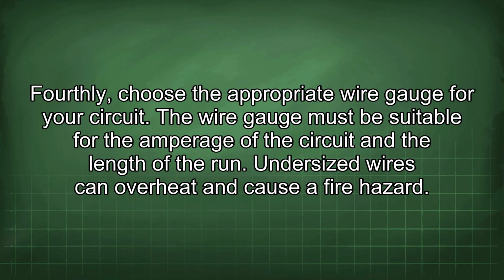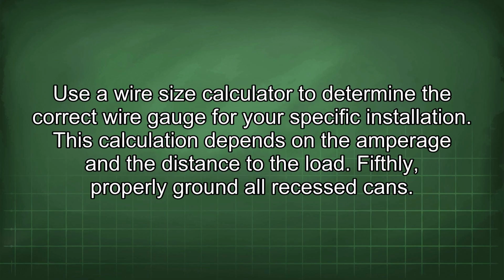Fourthly, choose the appropriate wire gauge for your circuit. The wire gauge must be suitable for the amperage of the circuit and the length of the run. Undersized wires can overheat and cause a fire hazard. Use a wire size calculator to determine the correct wire gauge for your specific installation. This calculation depends on the amperage and the distance to the load.